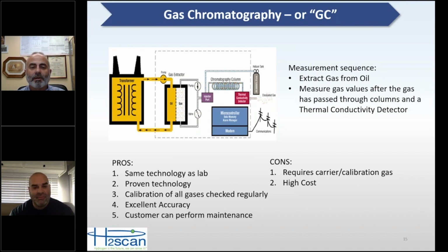This also does require ongoing calibration. So you want to check the calibration and adjust that calibration as those columns age. And so there are a couple of gas bottles involved with gas chromatography. The pros for this technology are that it is the same technology as the lab. It's very proven. The good thing is your monitor is calibrated continuously. So if you do go out of calibration when those columns are ready to get replaced, the monitor is going to let you know that.